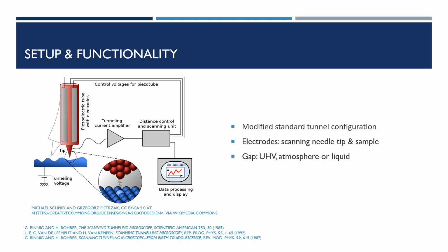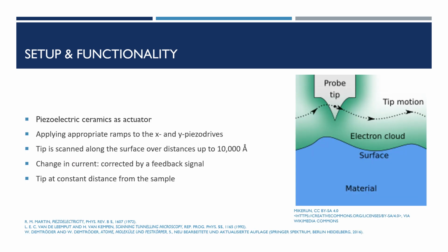It can also be filled with the atmosphere, but there is a problem that this contains oxygen, which can oxidize the surface or change the surface in other ways. The measurement can also be done in a liquid. The advantage there is that the sample does not change by contact with air. This is certainly the case for some biological samples whose natural environment is a liquid and which will collapse if it dries. By applying appropriate ramps to the X and Y piezo drive, the tip is scanned along the surface and follows its contours. So therefore the word scanning in the scanning tunneling microscope.